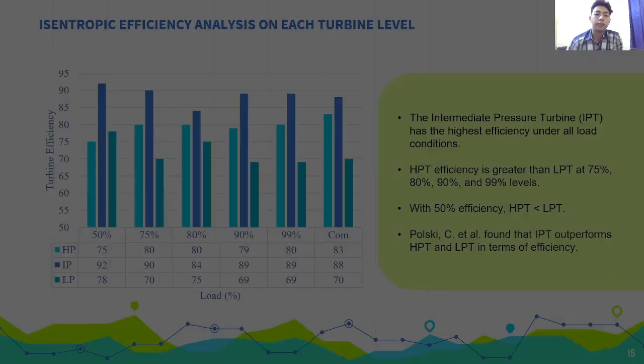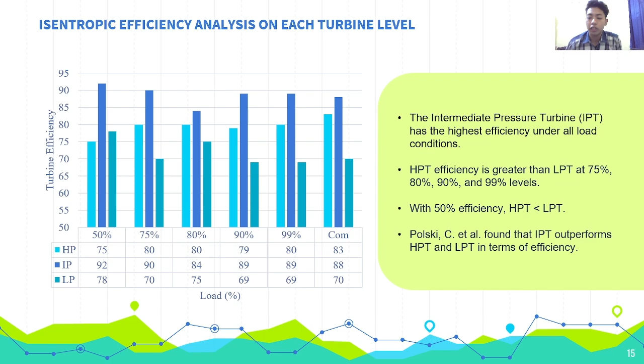This is an isentropic efficiency analysis. The intermediate pressure turbine has the highest efficiency under all load conditions. High pressure turbine efficiency is greater than low pressure turbine at 75%, 80%, 90%, and 99% load, and then at 50% load, the high pressure turbine efficiency is less than the low pressure turbine. Polsky et al. supported that the intermediate pressure turbine outperforms the high pressure turbine and low pressure turbine in terms of efficiency.